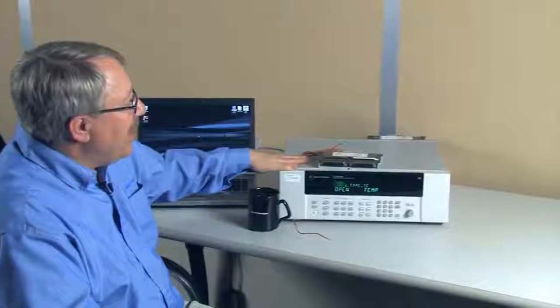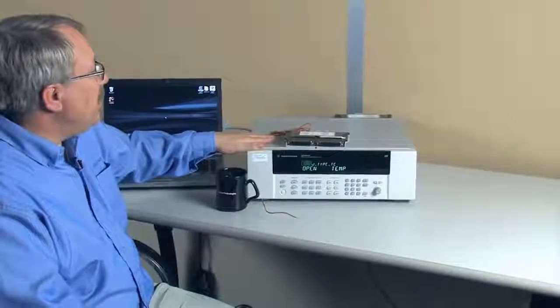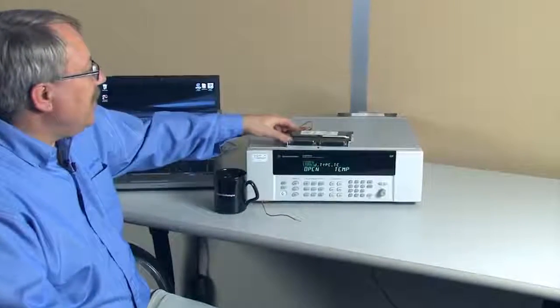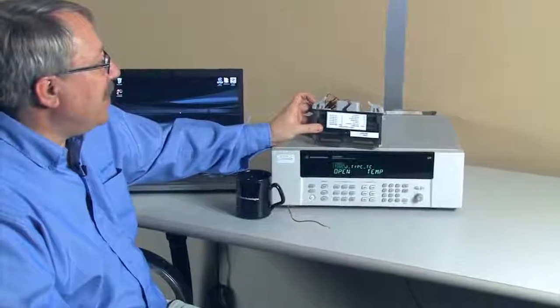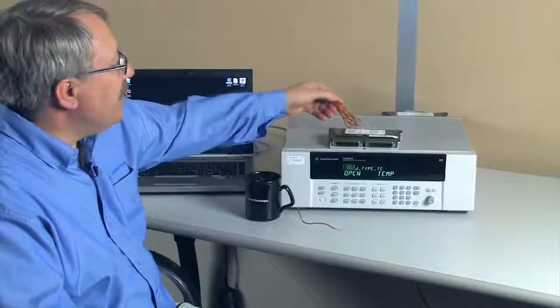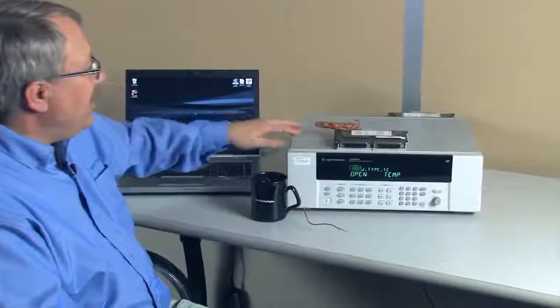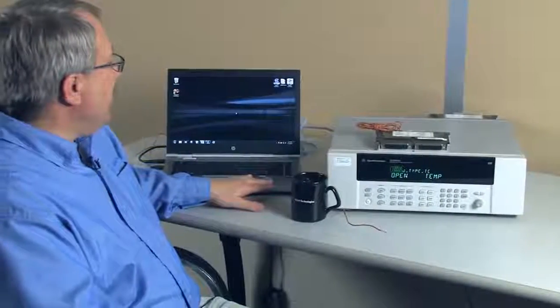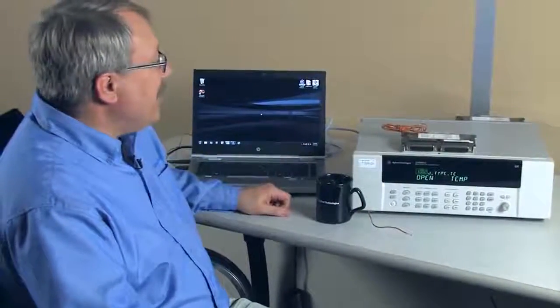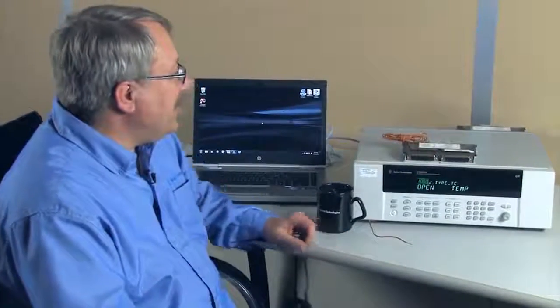I have a 34980 switch control unit with a MUX card installed. Connected to the MUX card is a terminal block just like this one, wired to a thermocouple, J-type. The 34980 is then attached to the laptop with a LAN cable. That'll be useful when we talk to the 34980 over LAN.